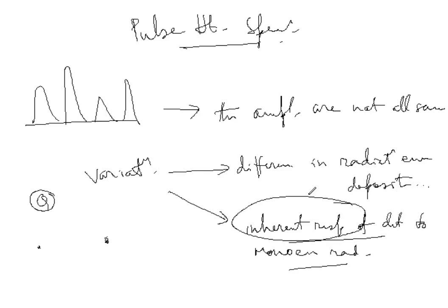Now the pulse amplitude distribution is a fundamental property of the detector output, which is important because it gives us information about the incident radiation, and also using the amplitude we can get information about the detector itself, whether the detector is working properly or not.